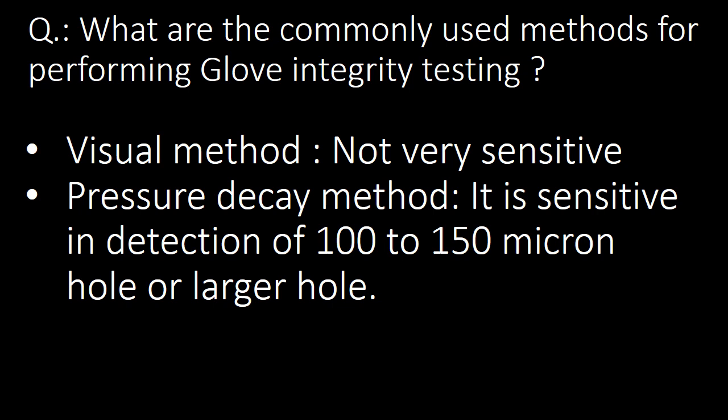The next important question: what are the commonly used methods for performing glove integrity testing? There are two commonly used methods: the visual method and the pressure decay method. The visual method can detect macro or major defects and is considered a less sensitive method, whereas the pressure decay method is the most preferred method and is sensitive in detection of 100 to 150 micron holes or larger.